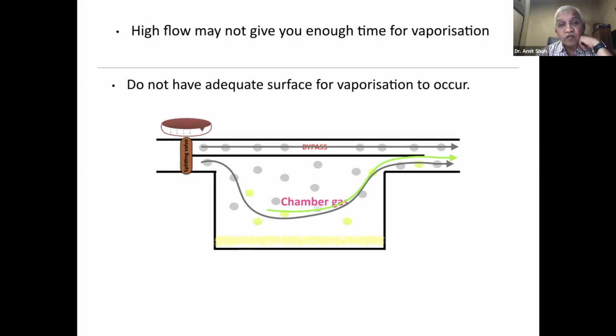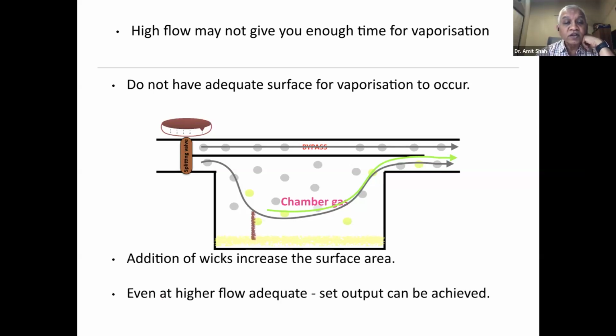So if you do not have adequate surface for vaporization to occur, what they've added was additional wicks. Okay, they've added additional compartments, and over the compartment they have kept a wick type of substance which will take the liquid into its part, which can be converted into the vapor. So they have basically increased the surface area. So by increasing the surface area, even at higher flow, the set output can be achieved. Suppose you put 8 liter flow and 8% sevoflurane concentration for the inhalation induction, it still should make an output of 8% by increasing the surface area. Okay. So by addition of wicks and the compartment, it increases the surface area.